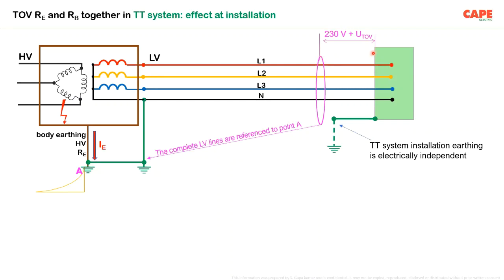Basically, between the body of your equipment and the phase and neutral conductor, you have a voltage stress. And if your equipment is unable to withstand this particular stress, of course, your equipment is going to fail. We are going to look at these voltage limits and some of the techniques which can be applied or which is recommended in the standard to get rid of this particular problem.